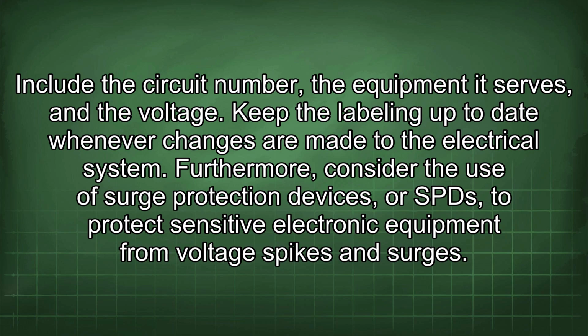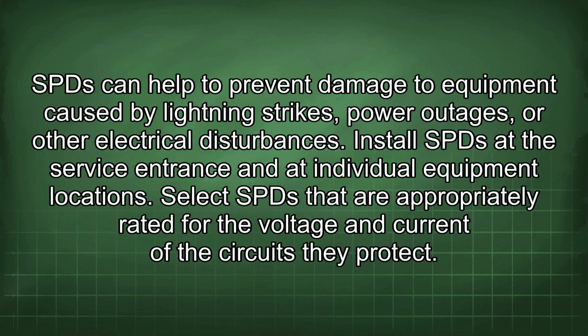Furthermore, consider the use of surge protection devices, or SPDs, to protect sensitive electronic equipment from voltage spikes and surges. SPD can help to prevent damage to equipment caused by lightning strikes, power outages, or other electrical disturbances. Install SPD at the service entrance and at individual equipment locations. Select SPD that are appropriately rated for the voltage and current of the circuits they protect.